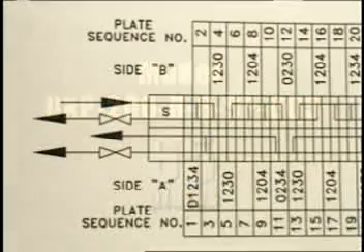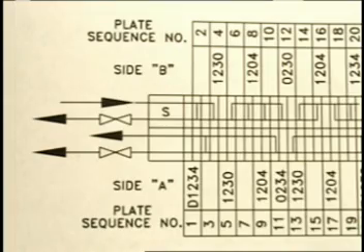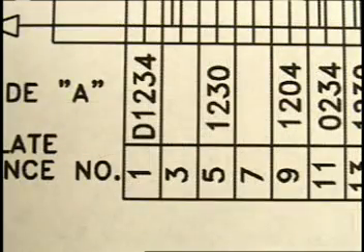There is also a box containing a four-digit number. This number tells you the plate porthole piercing. As an example, a plate designated 1, 2, 3, 4, or not designated with a number at all, will be a plate that has all four portholes pierced.